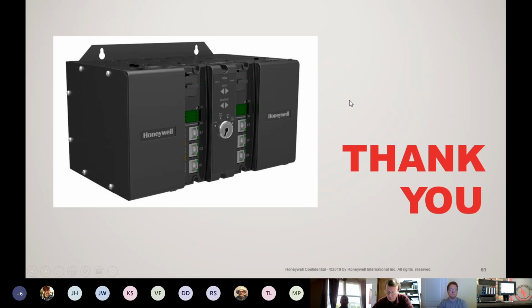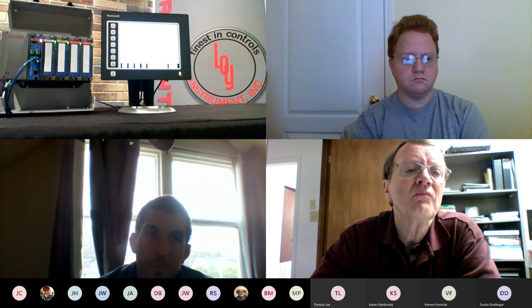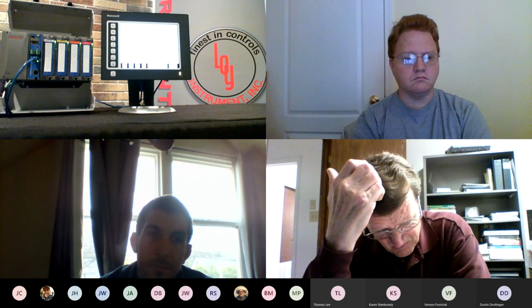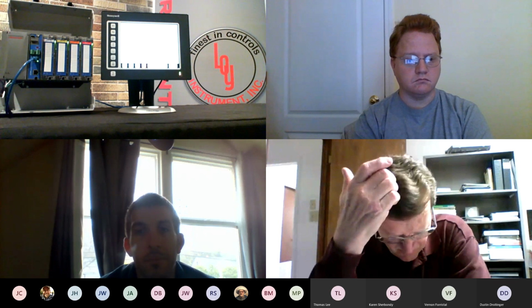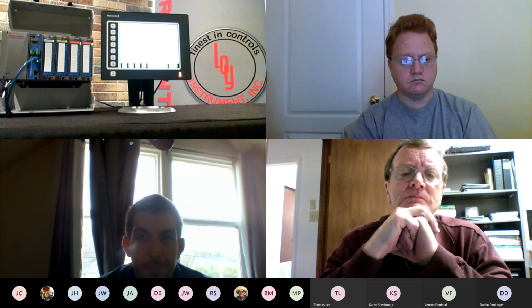So that wraps up the presentation here on the HC900. What I'm going to do is power up; I have my computer currently connected to a live HC900 I/O rack along with the display. The nice thing about the display is that if you have a network with a static IP address, then you can open up a standard web browser and browse the displays in the HC900 without any special software, and it allows very nice remote connectivity into the process to see what's going on. So we're going to look at a couple of the standard displays that are out of the box from the HC900, and I will go ahead and share with you. Let's see here. Okay, desktop.